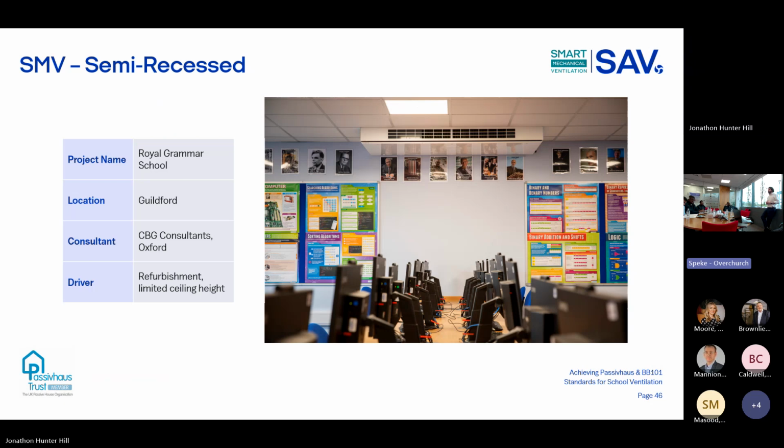But I find a lot of people saying that putting the unit in the middle of the room is best. What you want to do is put it as far from the centre of the room as possible, the longest throw. If you're thinking specifically in terms of cross contamination, what if you ducted your grills inside the room? There's no reason you couldn't have the unit right up against the external wall and only duct it after the supply grill into the room.